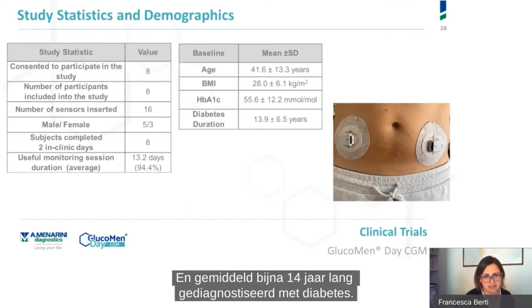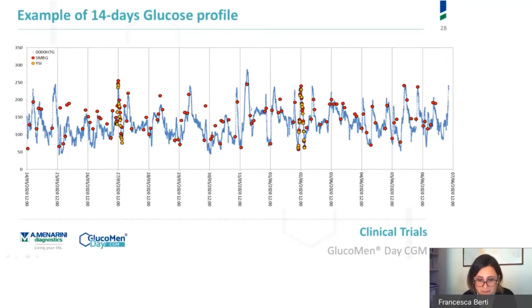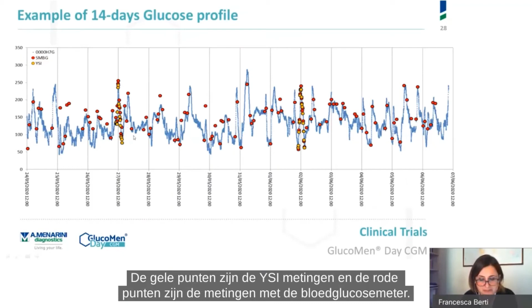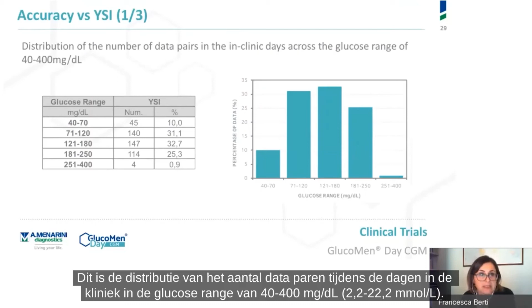This is an example of the CGM profile on the entire 14 days monitoring period. The 2 in-clinic days are clearly visible here, and we can see how the system correctly followed the glycemic excursion. The yellow dots are the YSI reference, while the red dots are the SMBG reference. So first of all, the accuracy versus YSI. This is the distribution of number of data pairs during the in-clinic days across the glucose range between 40 and 400 milligram per deciliter.